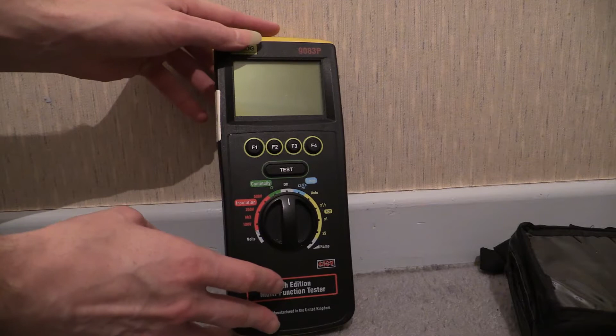And that's where these multi-function testers started coming onto the market. They're generally referred to as MFTs, or multi-function testers. The idea being, of course, you've got one unit that'll do RCDs, it'll do the PSCC test, it'll do continuity, and it'll do insulation resistance.